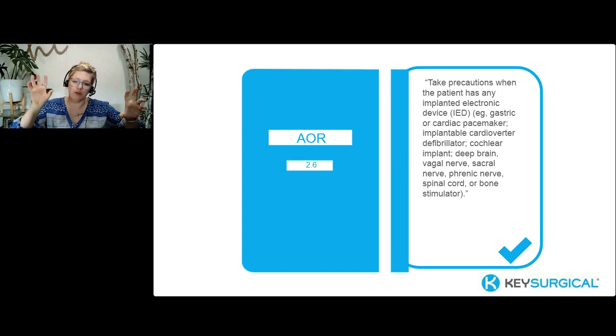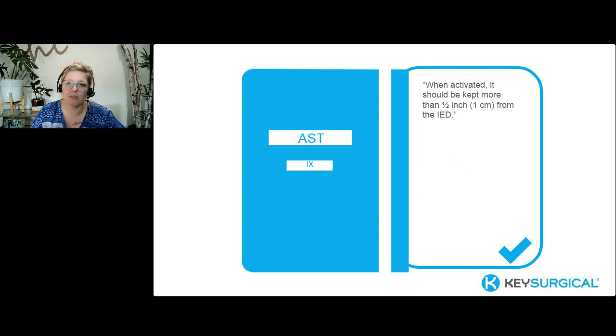But the other thing we kind of don't really talk about, maybe, or maybe we can now, which is great, is the functionality of that device. If you have electrical current that flows through a device, it might not cause a skin burn or skin damage, but it might make that device non-functioning, or it might change the settings within that device. So that's why we want to take extra care with any of those devices. And AST just has some very practical advice. When activated, the active electrode should be kept more than an inch or more than a half an inch from an IED, from any implanted device.